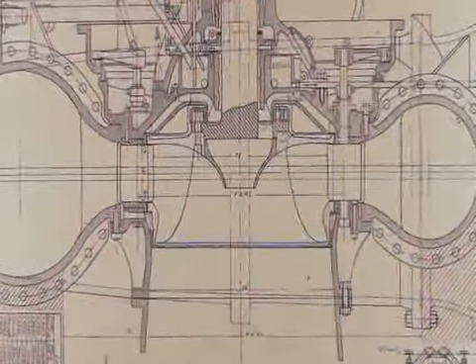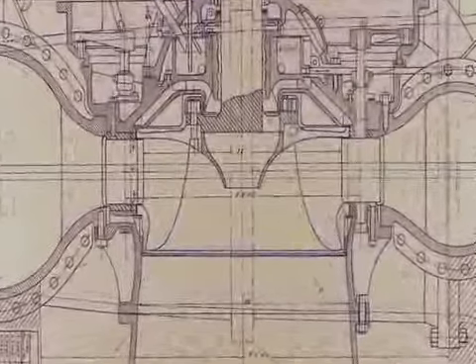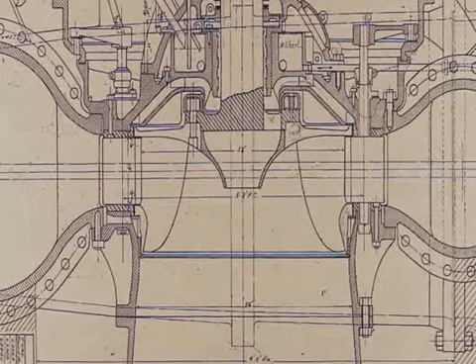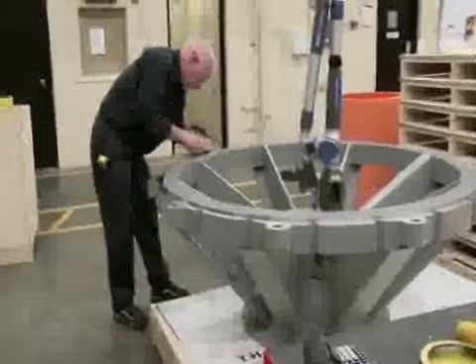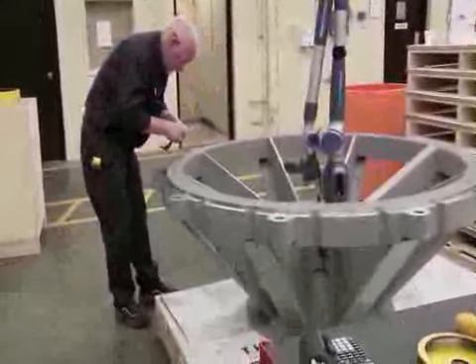The lower main guide bearing ensures that the shaft supporting the turbine below runs true, and positions the runner in the center of the scroll case. The second oil-lubricated guide bearing is typically located within the thrust bearing assembly, above the generator, and poses little risk of leakage beyond the powerhouse.